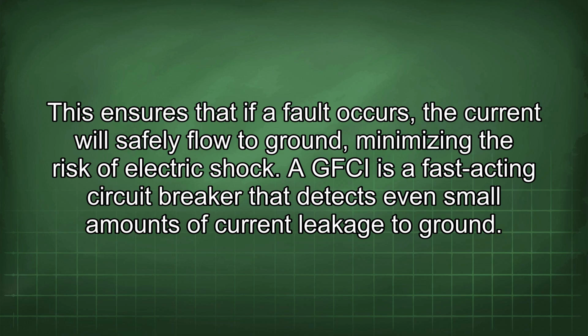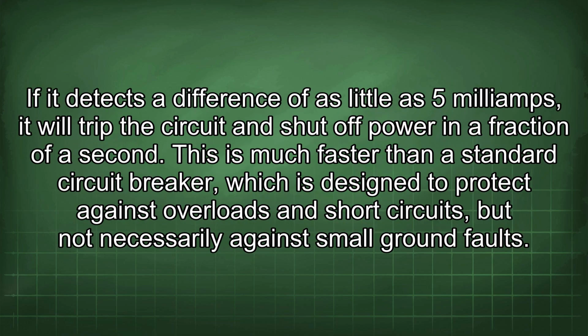A GFCI is a fast-acting circuit breaker that detects even small amounts of current leakage to ground. If it detects a difference as little as 5 milliamps, it will trip the circuit and shut off power in a fraction of a second. This is much faster than a standard circuit breaker, which is designed to protect against overloads and short circuits, but not necessarily against small ground faults.